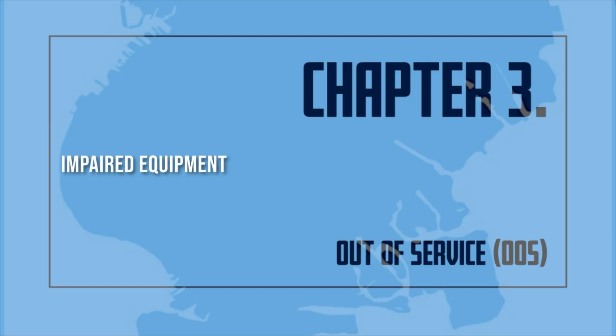Underground service mains, water storage tanks, fire department connections, control valves, and fire and/or booster pumps that are out of service and are considered vital to the system are required to be tagged, following procedures outlined in Chapter 14 of the National Fire Protection Association, number 25, 2002 edition. Tags placed at control valves shall indicate the level of impairment or defect as follows.